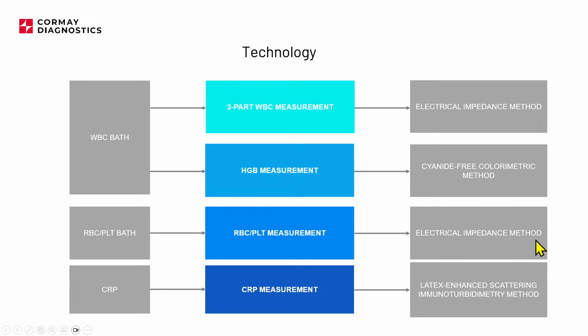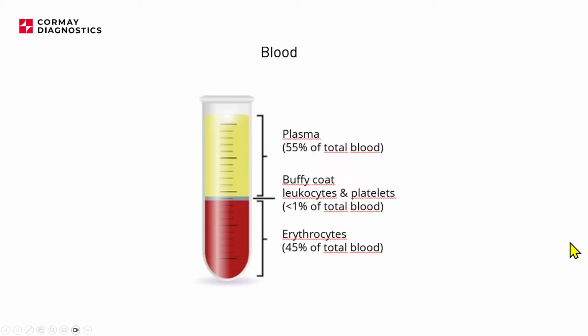the electrical impedance method is used. In the CRP chamber, device will measure the CRP concentration. So here is the name of the method. So it's latex enhanced scattering immunoturbidimetry method. So this is the key name, scattering, right? So we are not measuring the light which is transmitted, but we are measuring the light which is scattered by the sample which is in this chamber. And later on some other slides, we have more information about those things.